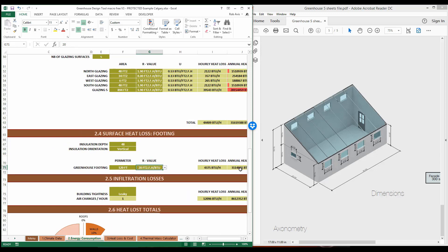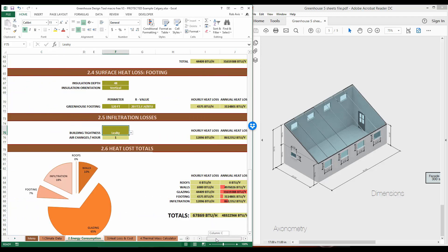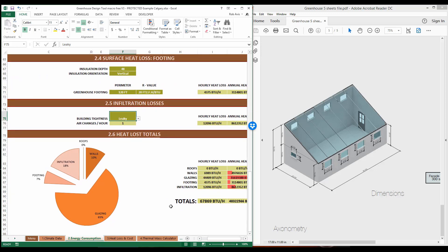Again, it shows us our heat loss there. We're going to assume that our building is leaky as it's a greenhouse. As a result of all the data we've input, we can tell that this greenhouse is going to have a peak heat loss of 67,869. Keep in mind that this model assumes heat loss is likely happening at night when there's no sun, at which point a thermal curtain could be employed. Notice that the glazing is the primary culprit for heat loss, so if the R value of the glazing was increased by a factor of 2 at night, we can assume the peak heat loss could be cut by a factor of 2 as well.